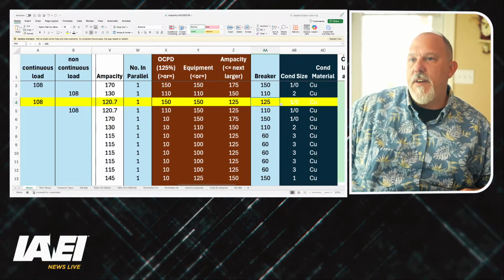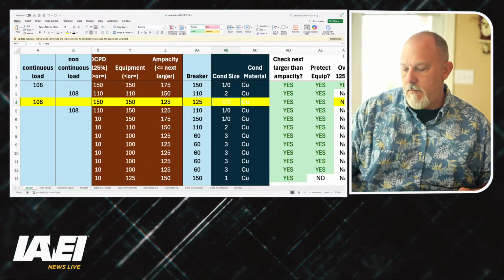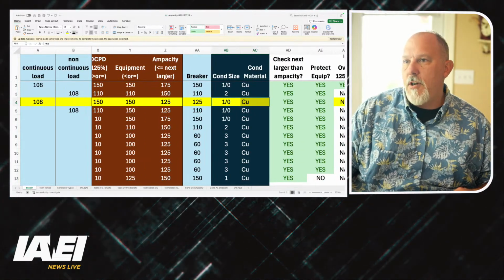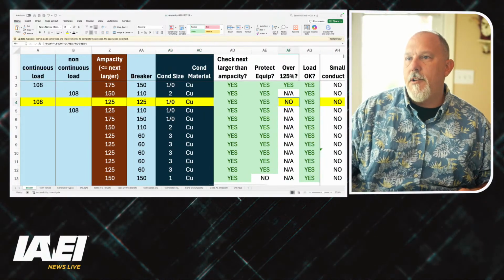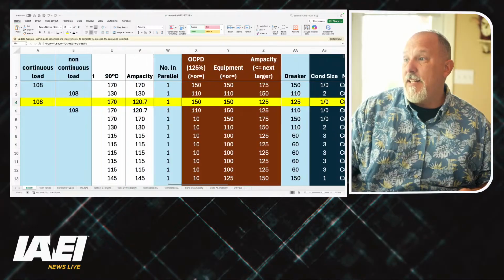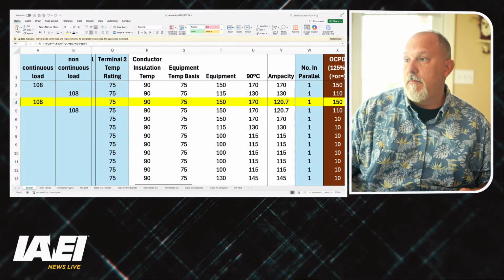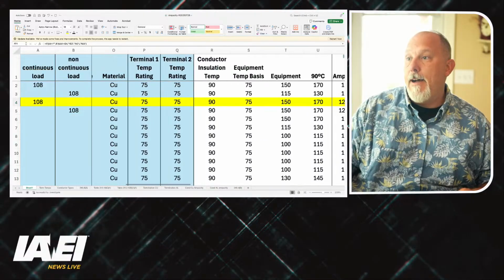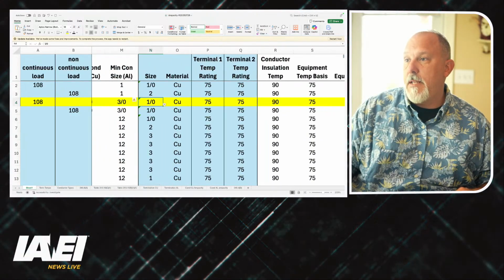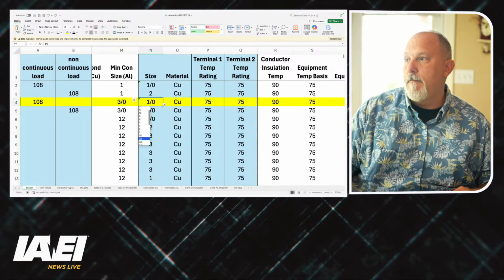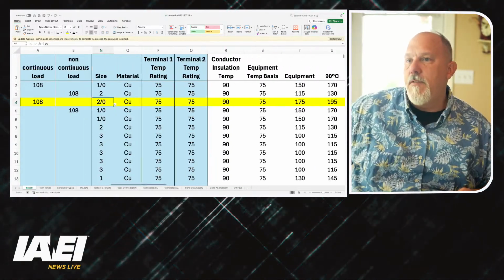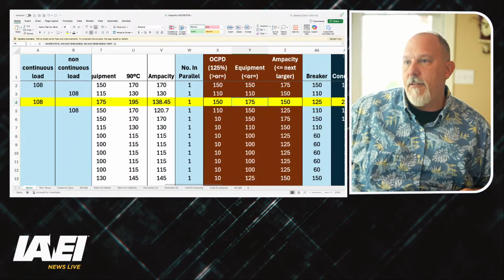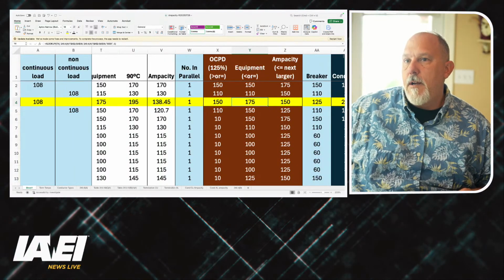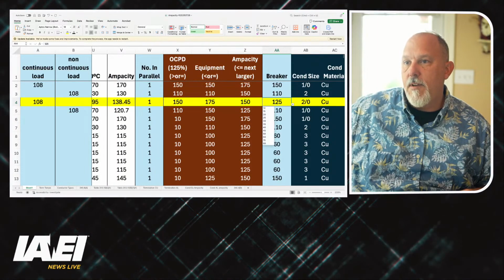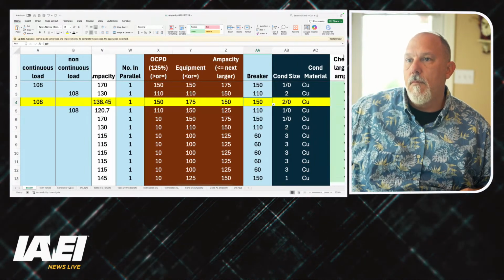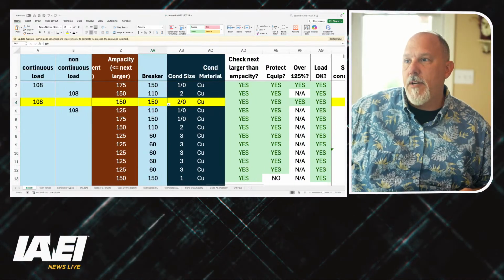So if I pick 125 to protect a 1/0 copper, I'm not over 125%. So I need to increase the conductor size. Let's pick this up to a 2/0. If I move that up to a 2/0, now I can have 175. I can put 150 on there now. There it is. Now I've met all my criteria.